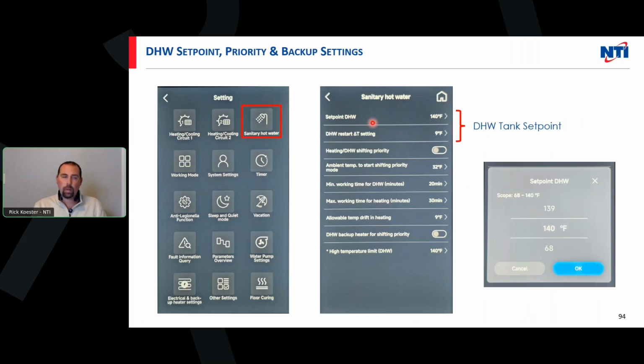From there, we have sanitary or domestic hot water. If I have an indirect being used, I can set my tank temp using our sensor. We'll monitor that temperature. We have our restart delta T, so when that tank drops down 9 degrees, we're going to fire and get that thing rocking. We can do heating and DHW shifting priority. Again, we can pick an outdoor temperature for when to have priority. So if I'm warmer outside and I don't need the priority of heating, cooling, I can set a temperature at which I want that priority. Those are cool little modes there. Then we have some minimum working times, high temperature limits, stuff like that.